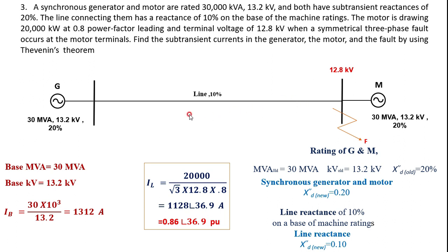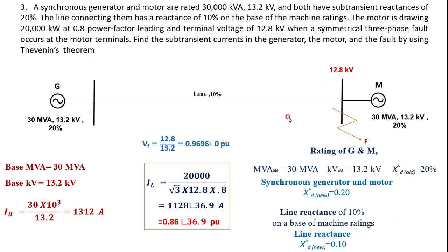The pre-fault voltage is 12.8 kV — before the fault occurs, the system is delivering load current at this voltage. Expressing this in per unit by dividing by the base voltage of 13.2 kV and taking it as reference at angle 0°, the pre-fault voltage is 0.9696∠0° per unit at the motor terminals.